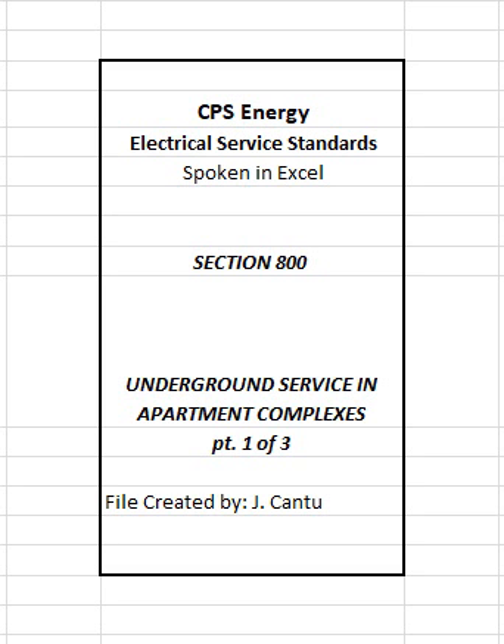804 Service lateral conduit. Service laterals shall be totally enclosed in conduits. All service conduits, elbows, and couplings shall be furnished and installed by customer from transformer or riser pole to meter loop. The conduit system shall be continuous except for watertight couplings, refer to Figure 802.